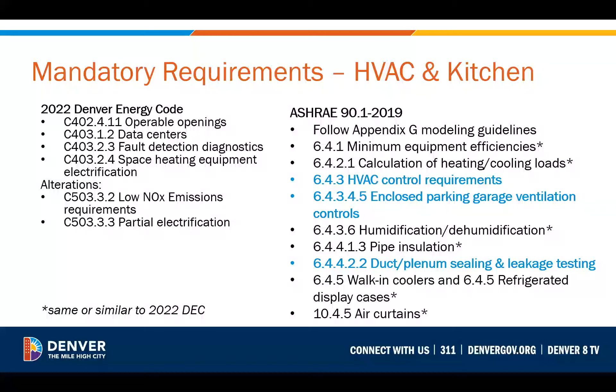HVAC control requirements have some slight differences, so teams will want to review those specific sections. Duct testing is required for ducts operating at 3 inches of static or greater. ASHRAE has that also, but adds testing for outdoor ductwork as well. Remember, testing does create a flag for the inspector. Also note, there are separate presentations that cover the electrification provisions in detail, and those are posted to the Denver Gov Energy Code website.